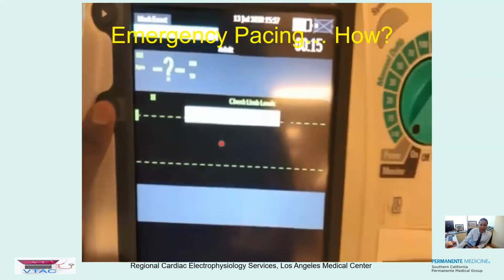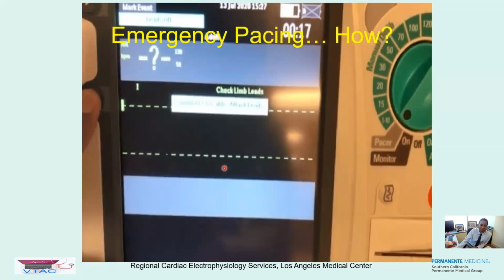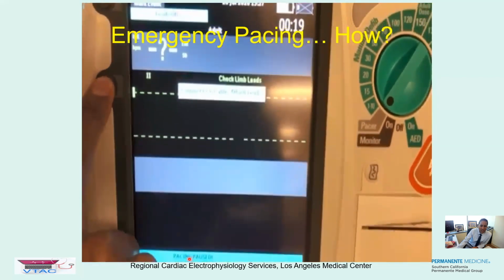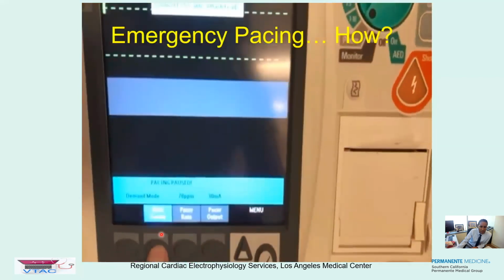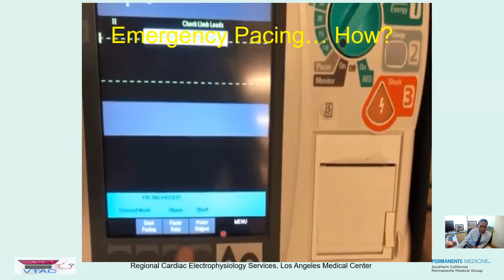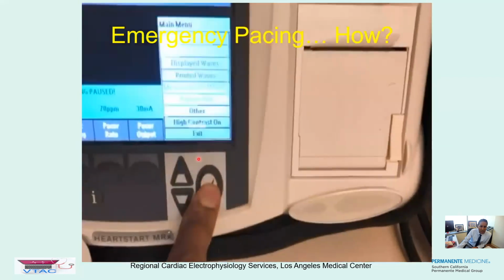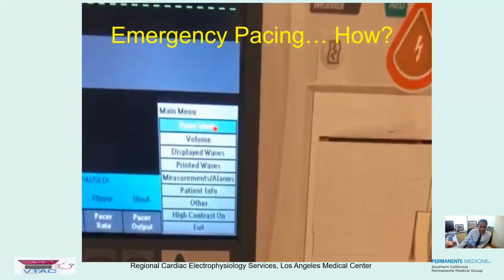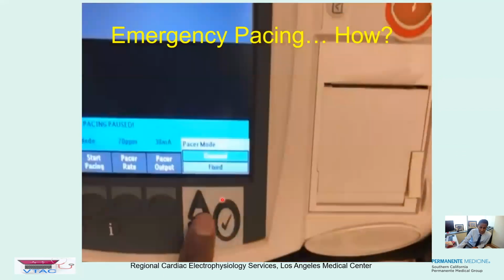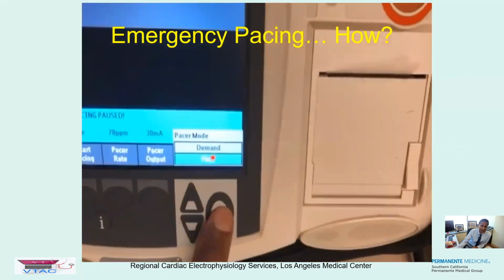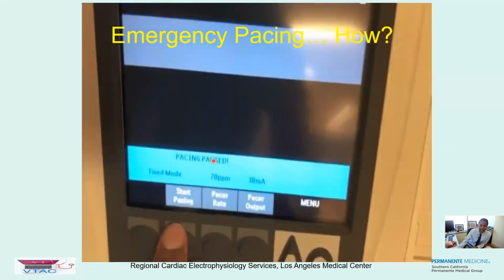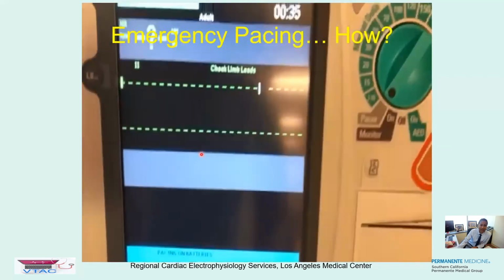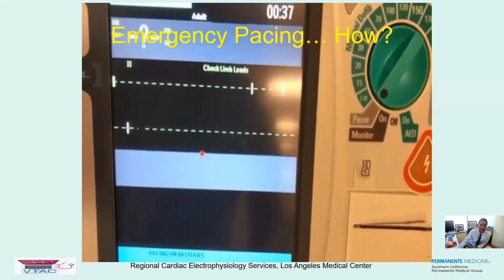And it's not pacing. So I go back in and check why it's not pacing. Start pacing is not working. The output doesn't work. So you have to go to menu, go to demand, go to mode, get to check. You have to change it from demand to fixed. Hit check — remember, the patient's in asystole. Hit start pacing. Boom. Pacing spikes.